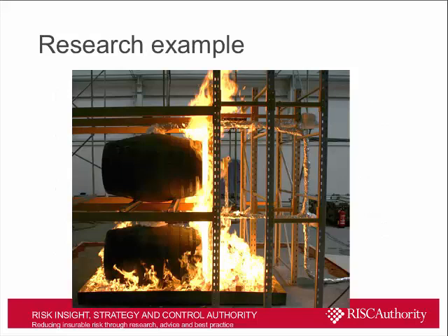Just as a quick example of research, this slide shows a picture of a research project I was involved with. This is an example of testing we undertook exploring the relationship between the time to open in-rack heads and steel softening due to a rapidly growing fire arising from a Class B, liquid fire. In this case, the steel in question loses half its structural strength at about 350 degrees Celsius. And the question was, how quickly will the sprinkler system kick in and have a beneficial cooling and protecting effect compared to the steelwork heating up and getting soft?